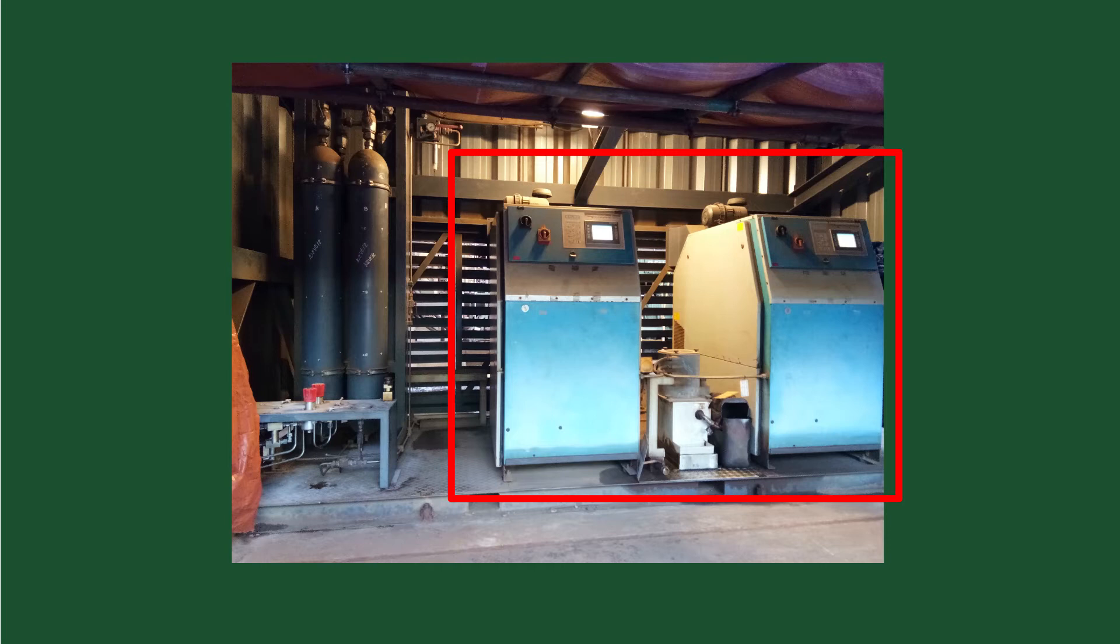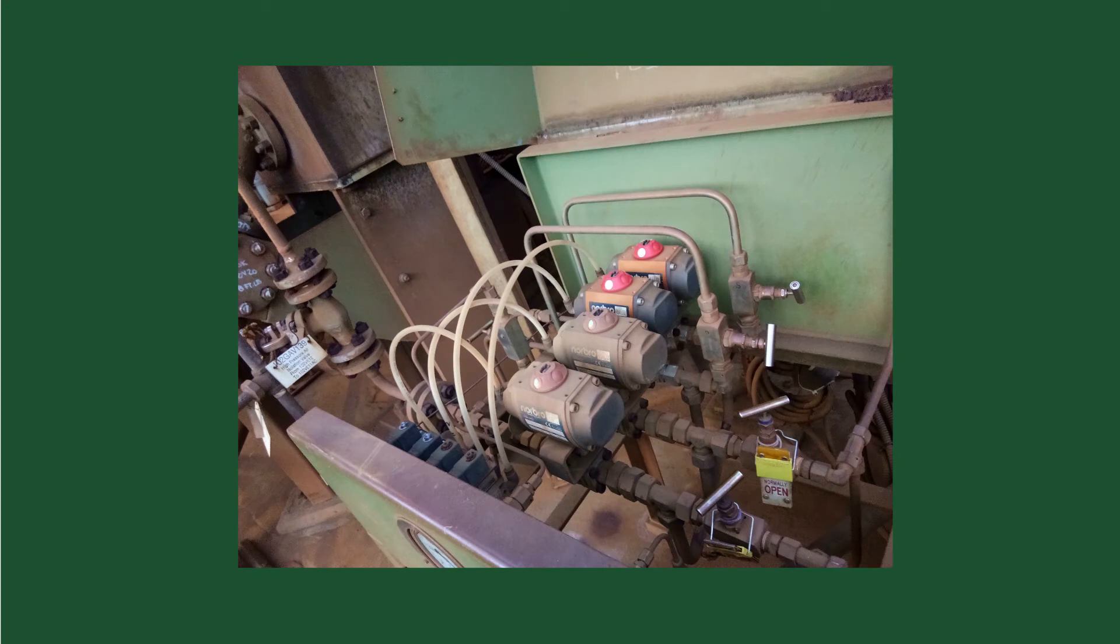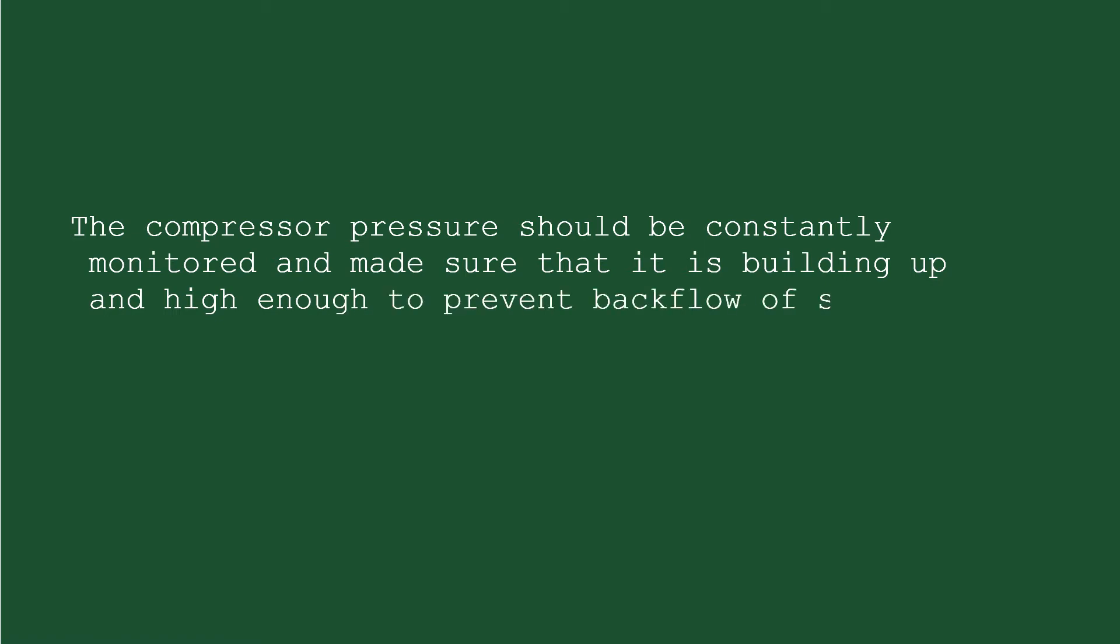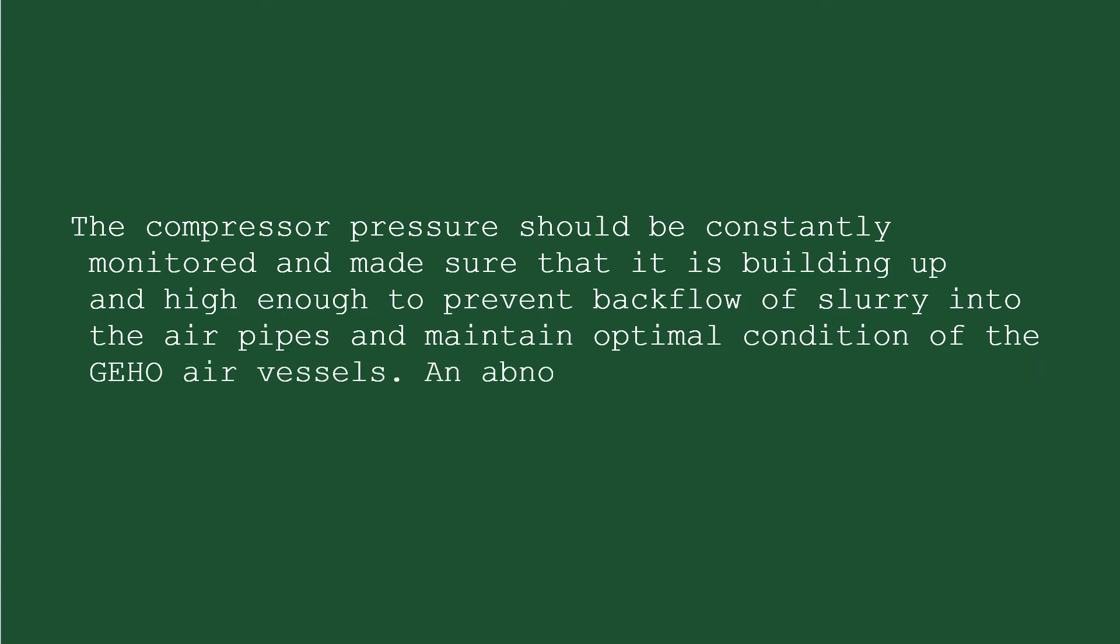That is, with one unit functioning as the master and one unit as slave. The air is supplied to suction and discharge air vessels via the level control valves. The compressor pressure should be constantly monitored and made sure that it is building up and high enough to prevent backflow of slurry into the air pipes and maintain optimal condition of the Geho air vessels. An abnormal trend in pressure should be reported immediately.